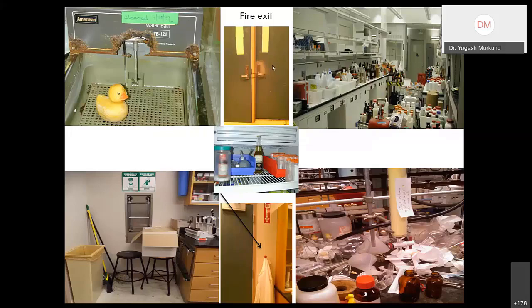You see this door, it's a fire exit, and it has been locked this way. If someone is running this side for an emergency, probably it will take a long time for them to open this door. I don't know what has been kept behind that also. You certainly don't want storage boxes and all those things kept on your work benches. Untidiness is certainly bad, we all know that, but sometimes things happen. You can see on this door, a fire extinguisher is kept and someone has kept their apron there. So if someone required it in an emergency, probably they will not even be able to locate that.